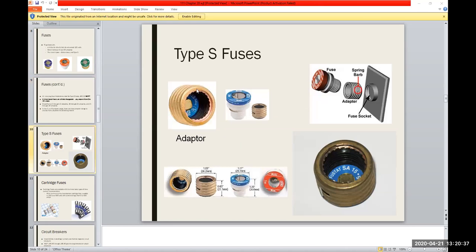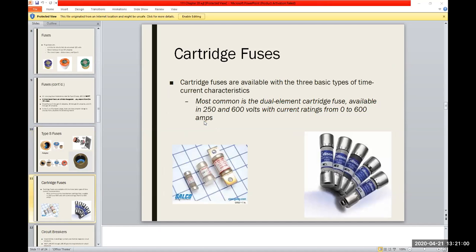But yep, there is a wonderful little thing. They made adapters for these, so you could screw it into the fuse panel and then go up to the next size and use a different size, like a 15 to a 20, or 20 to a 30 if you wanted. But like I say, a lot of people never even changed the corresponding wiring, so those got to be a problem. Now, we will take a look at cartridge fuses. These are very widely used, and they come in different flavors.